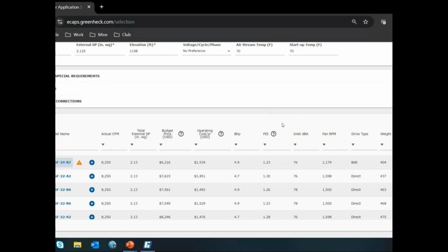Oh, not a problem. All right, so I'm picking this blower. My criteria right now, right off the bat: I want to pick an efficient fan. By the way, if you use efficiency to verify your fan selection is a good one, and I recommend that, I even more recommend that this ends up on the fan schedule.